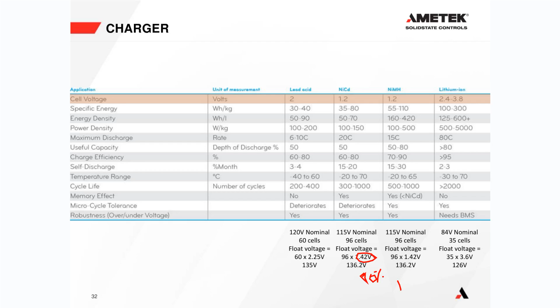NiCads are a little bit more complicated, and what the NiCad manufacturers have been doing is, because it is slightly complicated, they have now designed oversized cells so that you can charge them at 1.42 volts per cell and get all of the capacity that the data sheet specifies. In truth, it's usually about 80% of the full capacity of the battery. But if you bought a 100 ampere hour battery, then it would actually be sized at the factory at 120 ampere hours. So when you lose your 20%, you still get your 100 ampere hours. Hopefully that made sense.